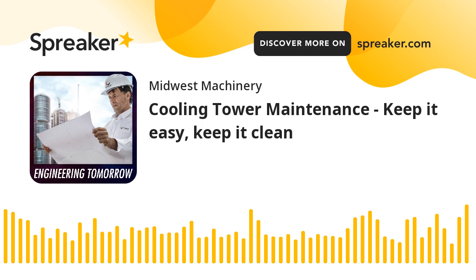One thing I've noticed over the years with basin heaters, or at least one thing that I want to stress, is to check the operation of your basin heater before it gets cold outside. Every year we get a lot of calls after the first big freeze of either the heater element not working or some part of it may malfunction on the older units. And what happens is all these basin heater parts get back ordered, and then you're weeks without the basin heater. So one thing I would recommend is that you check the functionality of your basin heater months before you hit that first freeze. When you do that, we can get you parts quickly. You can be in operation and you'll never have any downtime.